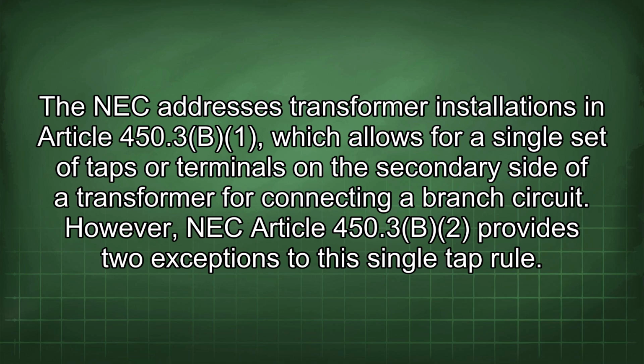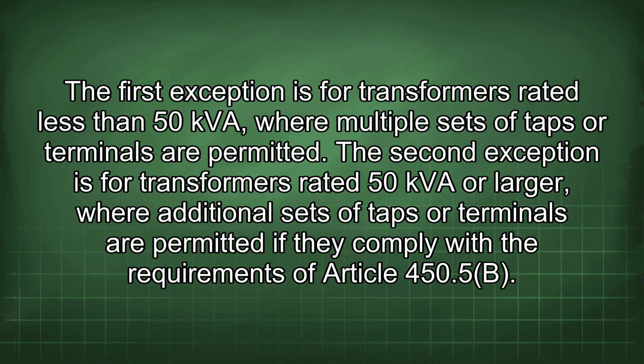However, NEC Article 450.3(b)(2) provides two exceptions to the single tap rule. The first exception is for transformers rated less than 50 kVA, where multiple sets of taps or terminals are permitted. The second exception is for transformers rated 50 kVA or larger, where additional sets of taps or terminals are permitted if they comply with the requirements of Article 450.5(b).